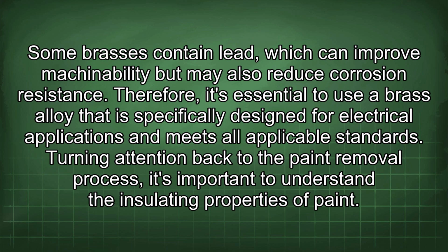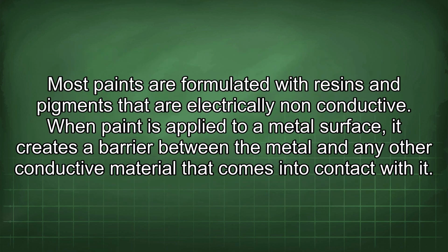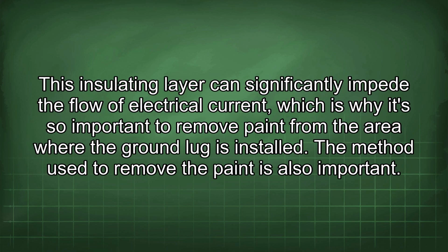Turning attention back to the paint removal process, it's important to understand the insulating properties of paint. Most paints are formulated with resins and pigments that are electrically non-conductive. When paint is applied to a metal surface, it creates a barrier between the metal and any other conductive material that comes into contact with it. This insulating layer can significantly impede the flow of electrical current, which is why it's so important to remove paint from the area where the ground lug is installed.